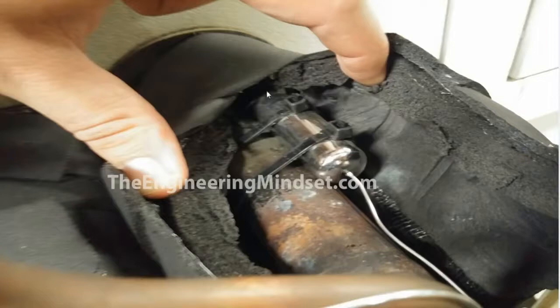Now this thermal bulb is filled with a refrigerant. When the superheat increases, this starts to cause a heat transfer across into the bulb. Usually this is covered with an insulation. You can see here I've just cut the insulation open so you can see it. It's important I replaced it back afterwards. But the superheat will transfer its thermal energy into this bulb. The bulb is filled with the refrigerant, and that refrigerant starts to boil and expand.